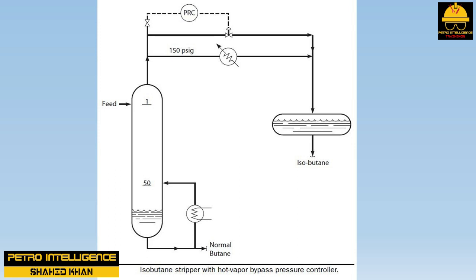To lower the tower pressure, the Hot Vapor Bypass Pressure Recorder Controller valve is closed. This forces more vapor through the condenser, which in turn lowers the temperature in the reflux drum. As the liquid in the reflux drum is at its bubble point, reducing the reflux drum temperature will reduce the reflux drum pressure. As the stripper tower pressure floats on the reflux drum pressure, the pressure in the tower will also decline. The net effect of reducing the stripper pressure was to greatly reduce the amount of isobutane in the heavier normal butane bottoms product. There is no doubt most of the improvement in fractionation was due to enhanced tray efficiency, which resulted from suppressing tray deck leaking or dumping. However, there was a secondary benefit of reducing tower pressure: increased relative volatility.